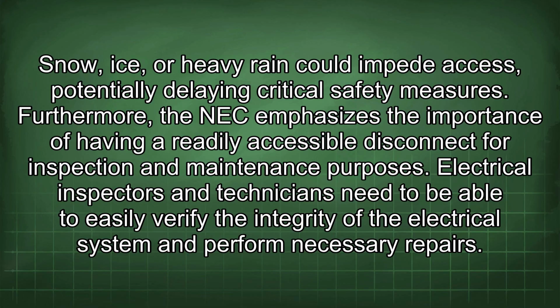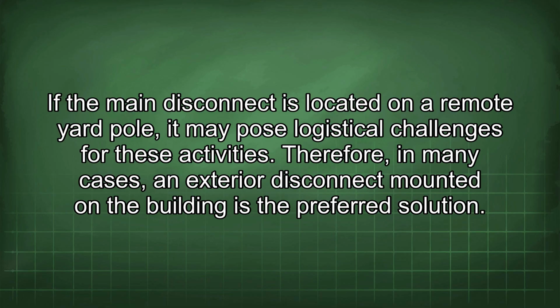Furthermore, the NEC emphasizes the importance of having a readily accessible disconnect for inspection and maintenance purposes. Electrical inspectors and technicians need to be able to easily verify the integrity of the electrical system and perform necessary repairs. If the main disconnect is located on a remote yard pole, it may pose logistical challenges for these activities. Therefore, in many cases, an exterior disconnect mounted on the building is the preferred solution.